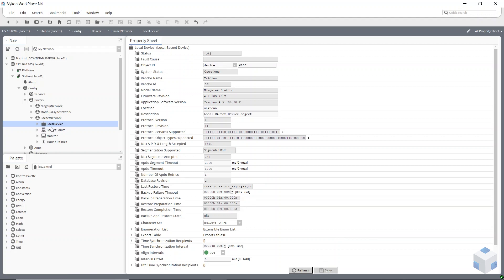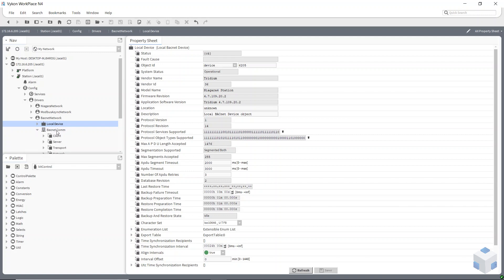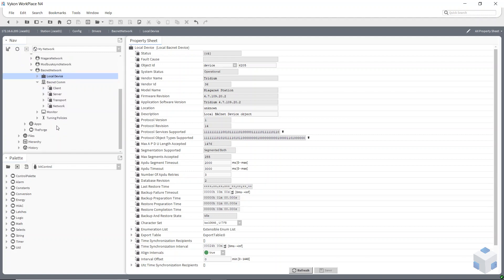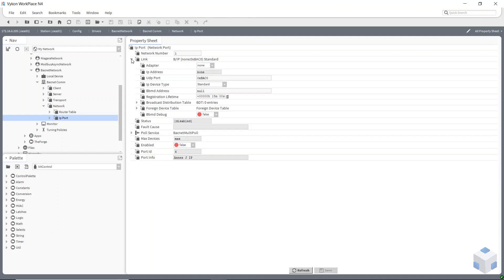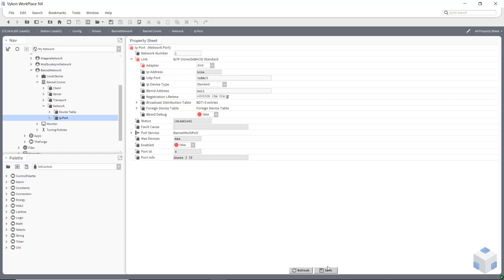The next two things are underneath our network which is underneath BACnet com. So buried quite deep down is our IP port. So if I double click on that, this is where I now have to select which of the two adapters I have on my Jace I'm going to be using. So I'm going to be using adapter port 1 which is en0. Port 2 is en1 so it's en0 I'm going to be using. Save that. So that's two things taken care of now.